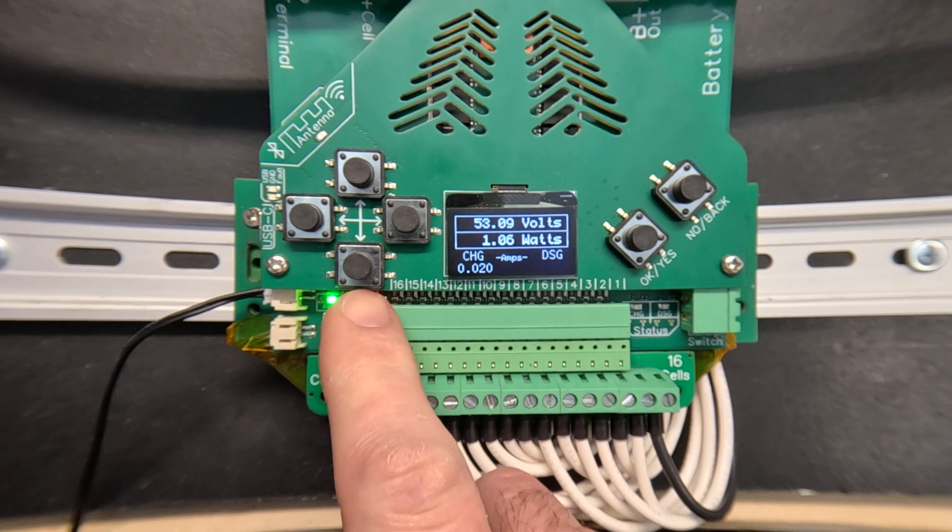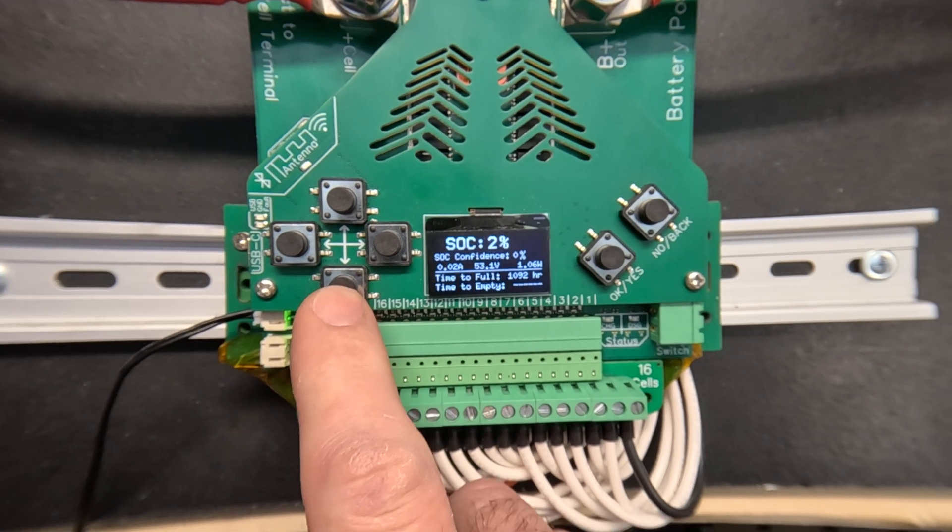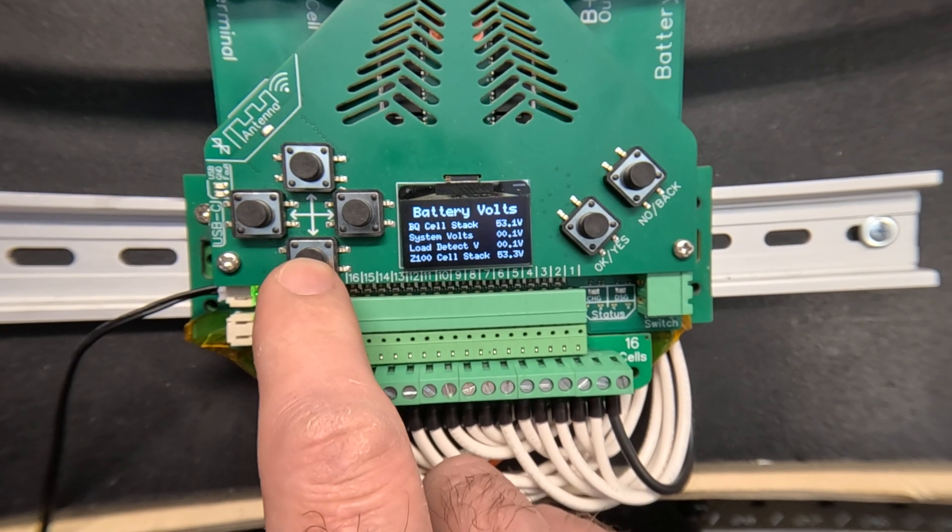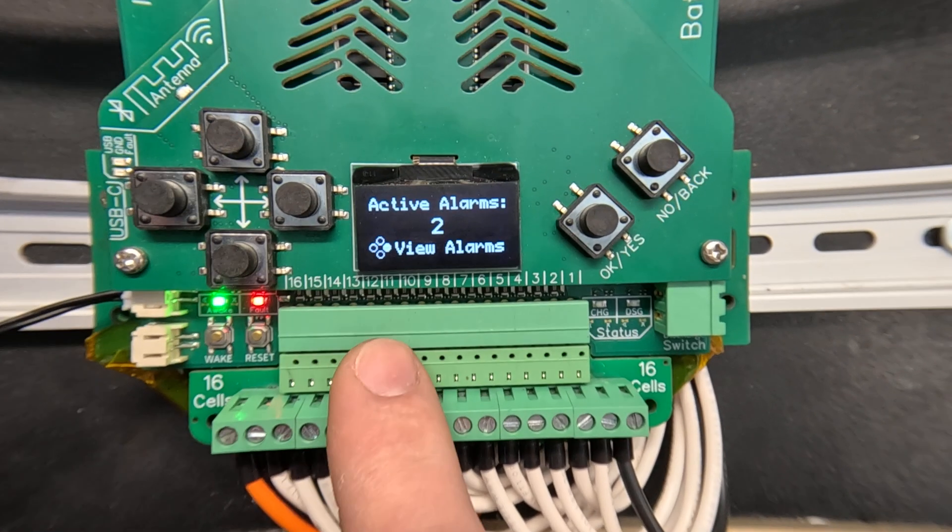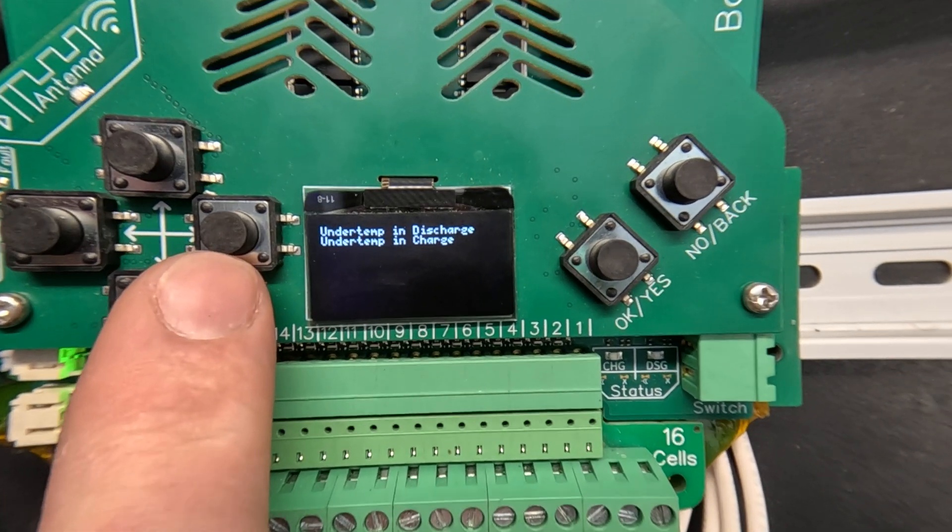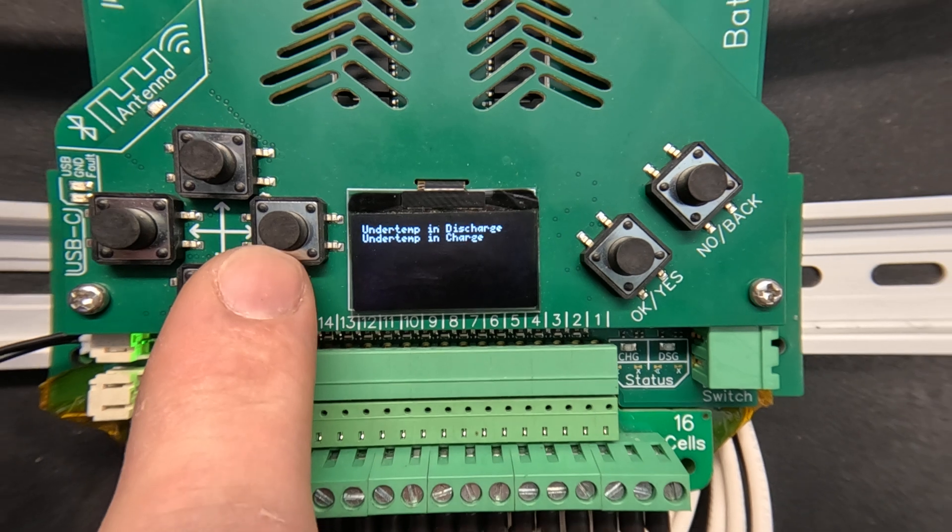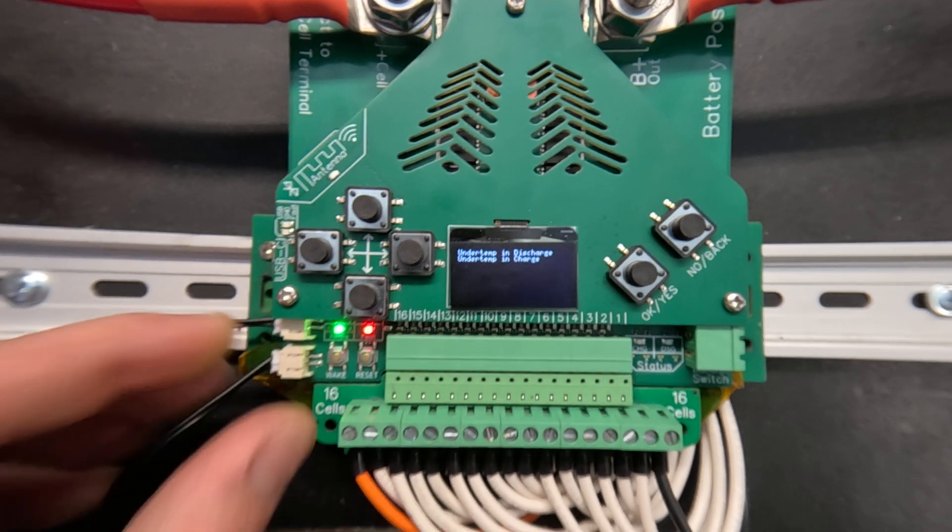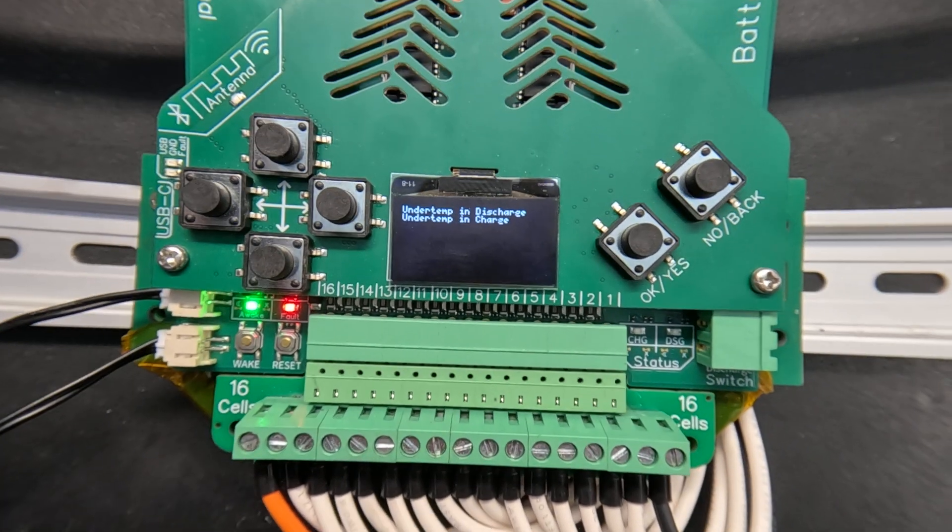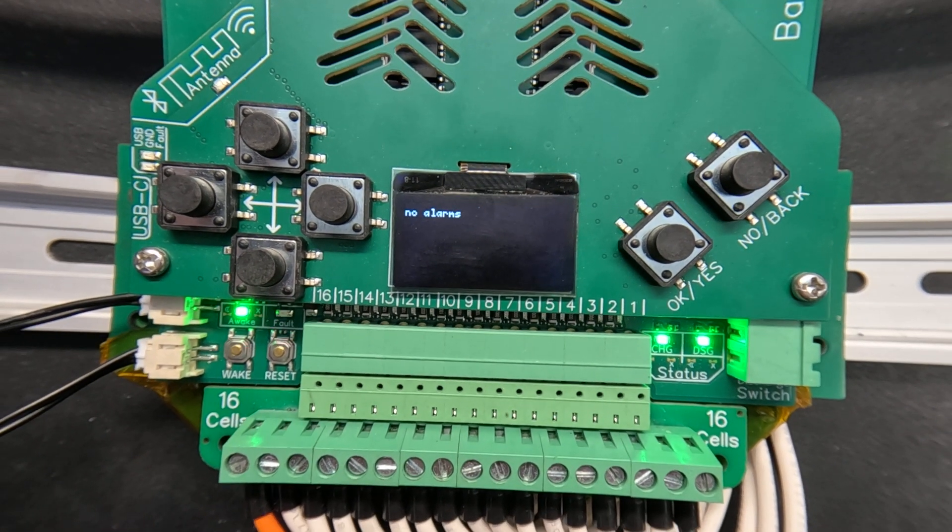You can view the alarms via the screen. Here we have two active alarms. That's reading under temp in discharge and under temp in charge. And if I put the temperature probe back those should clear automatically. Now it says no alarms and the outputs have switched on again.